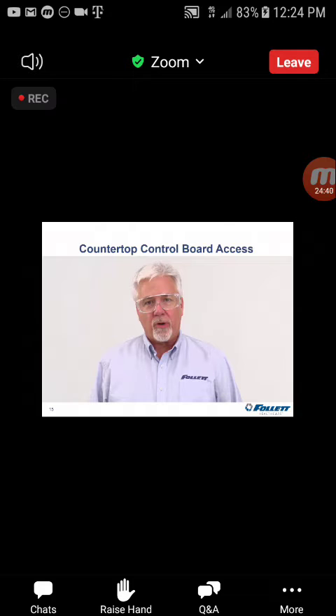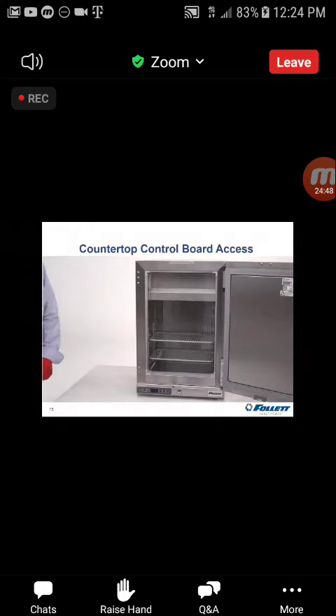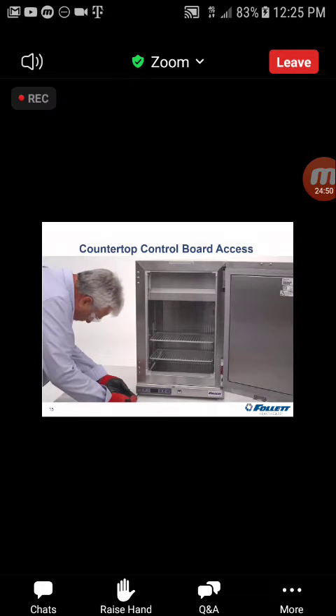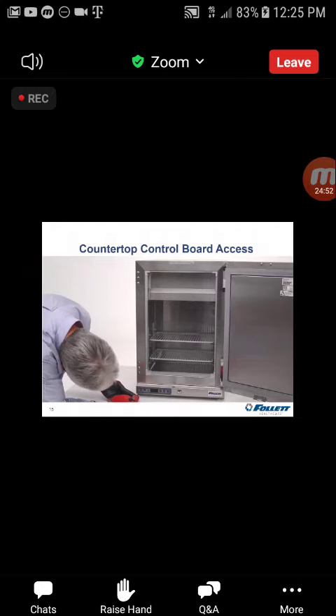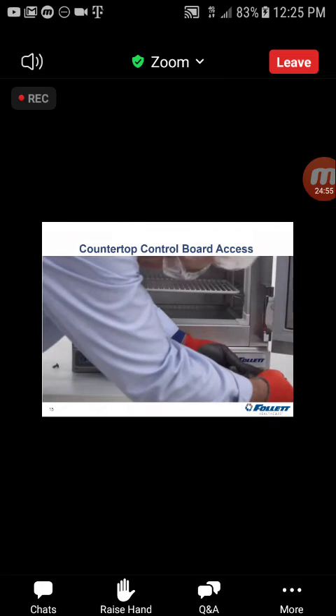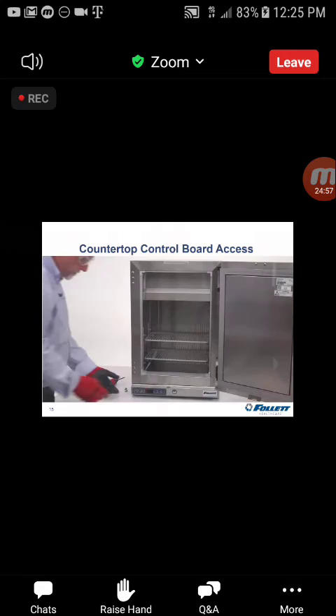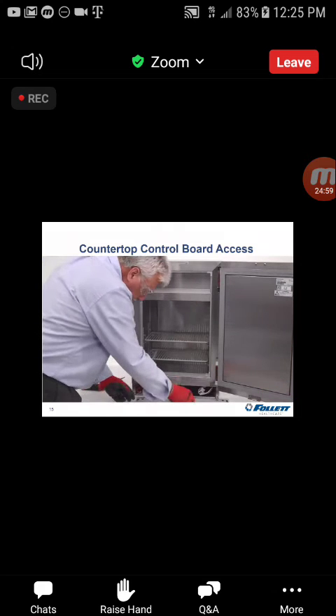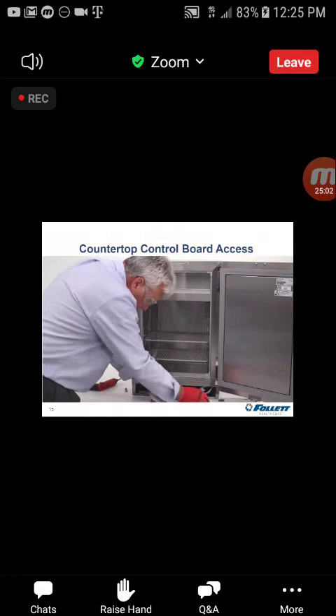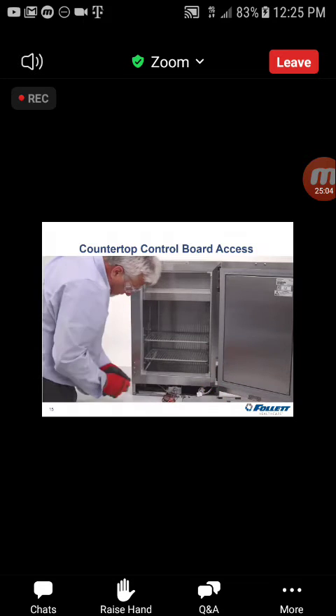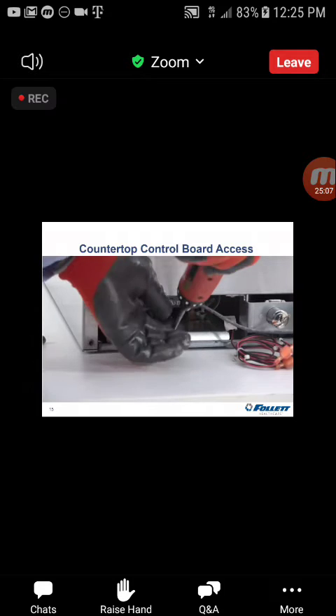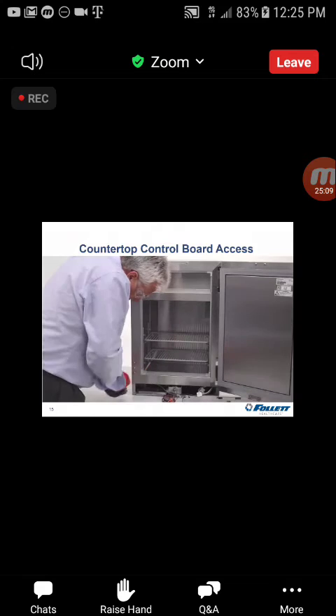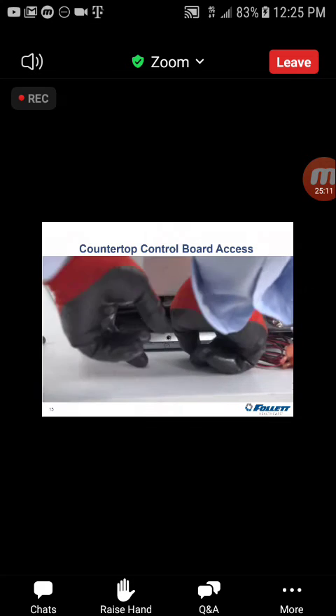To access the control board on a countertop refrigerator or freezer, unlock the door, open and prop it open, then remove the 2 Phillips head screws at the bottom right and left-hand corners to remove the front panel. Take care removing the panel. There are wires connected to the interface that are attached to it. Set the panel aside. Then, on the left-hand side, you will see a mounting plate with a Phillips head screw. Remove the single Phillips head screw and then gently remove the mounting plate and components.